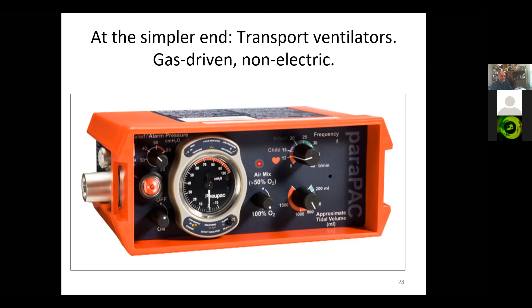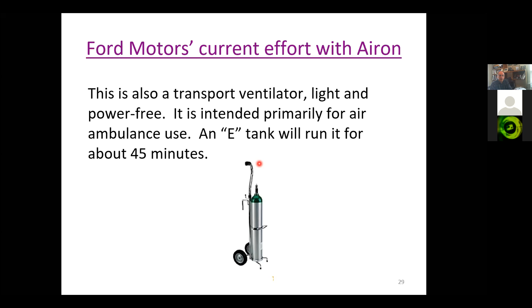Ford Motors is working with a manufacturer of these sorts of ventilators. It's light, it's made of aluminum, it is made mostly for air ambulance use. Notice that an E-tank will only run it for about 45 minutes. If you have a patient whom you're ventilating with an ambu bag, an E-tank might run for several hours. This requires quite high flow of oxygen. An E-tank has 660 liters of standard pressure, atmospheric pressure oxygen in it, and this will rip through it pretty fast. It doesn't have any provision other than swapping off to an ambu bag for continuing to ventilate the patient if all you have available is room air.